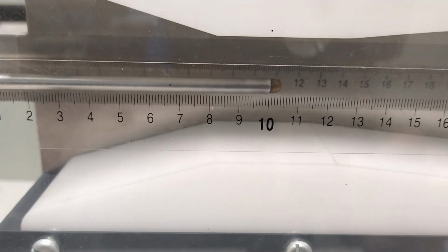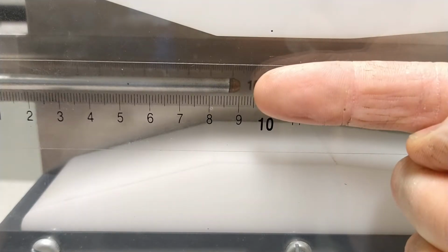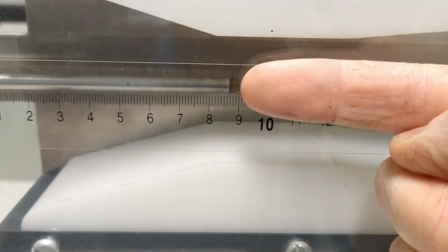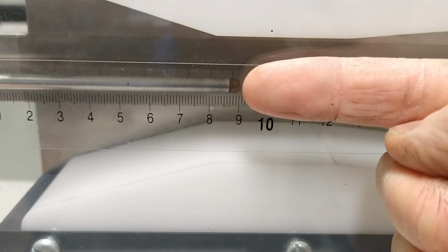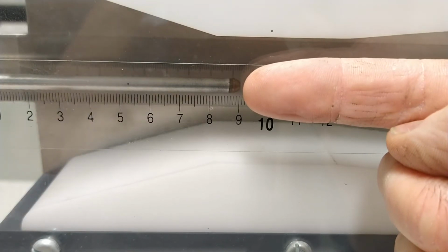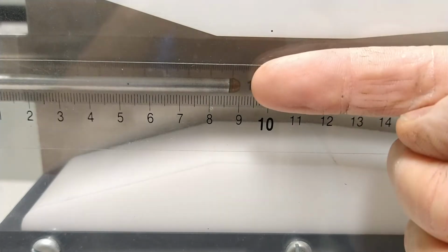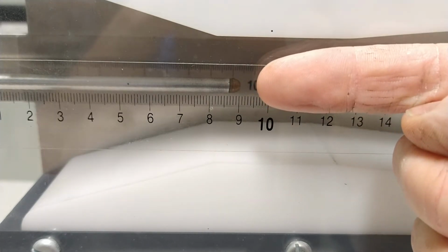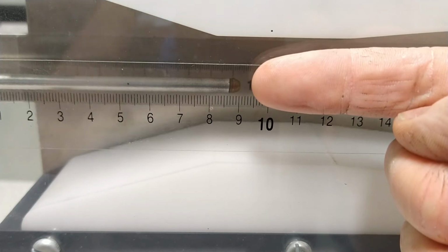When this thing is inside the Venturi, you have one pressure port that's facing directly into the airflow. The airflow is coming in this direction towards the pitot-static tube. You have one port directly at the front of that little brass cap, facing directly into the airflow. That's going to measure all the pressures within the system.